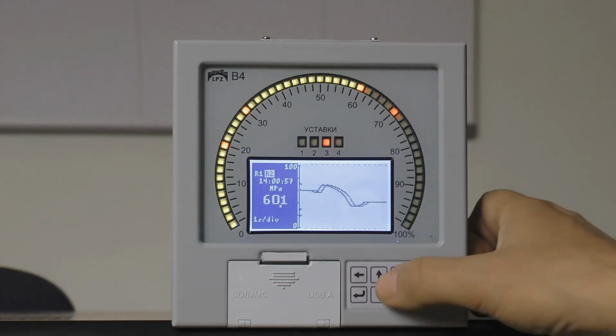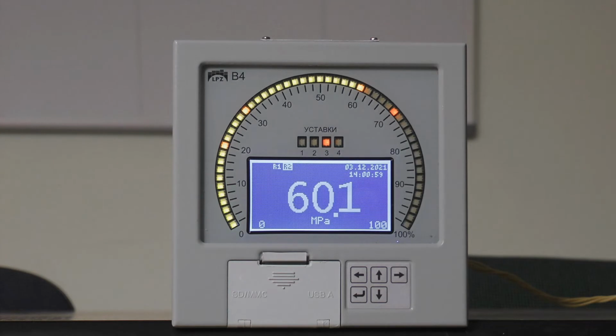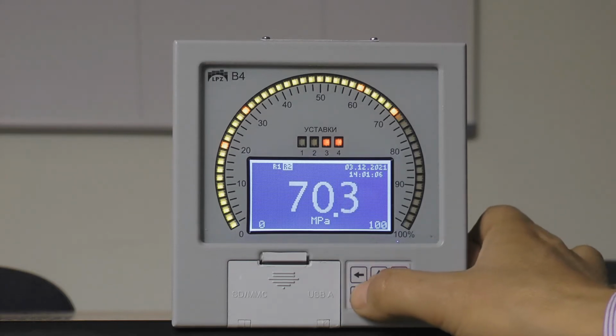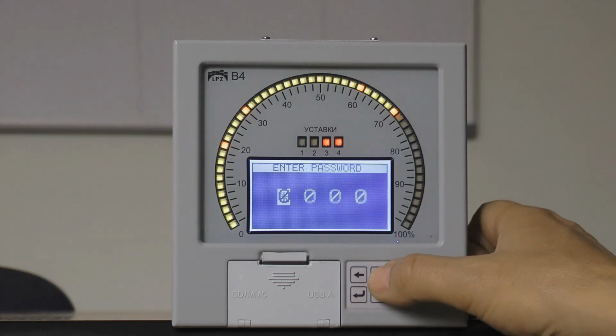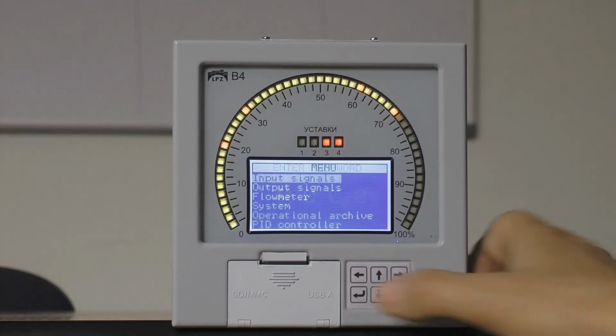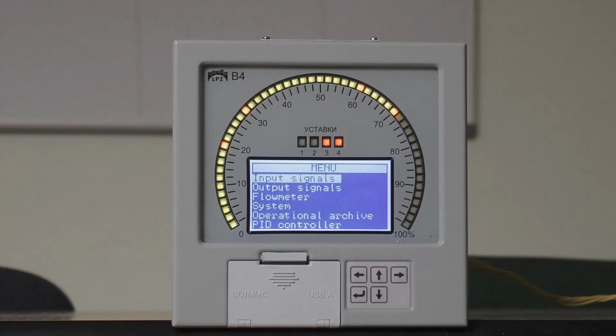And now I would like to go back to the main menu. To enter the main menu, we need to enter the password first, as that's the only way to see the setting menu. The password here is 1000, and we are entering it and going to the setting menu. Here you can adjust input and output signals, flow meter, system, operational archive, and PID controller. This time we aren't using the flow meter and PID controller.